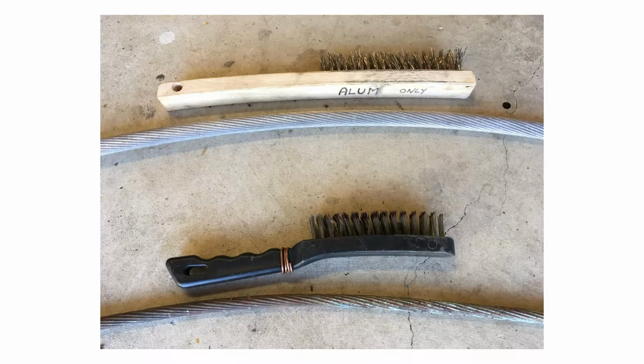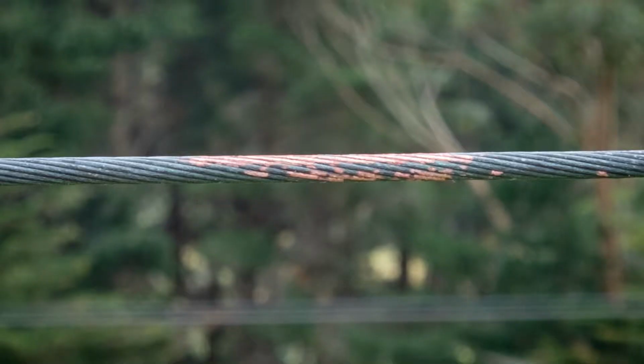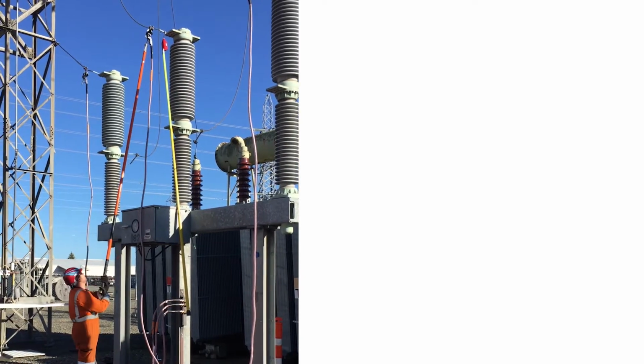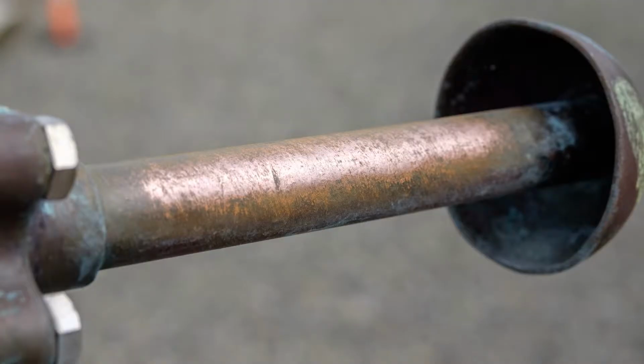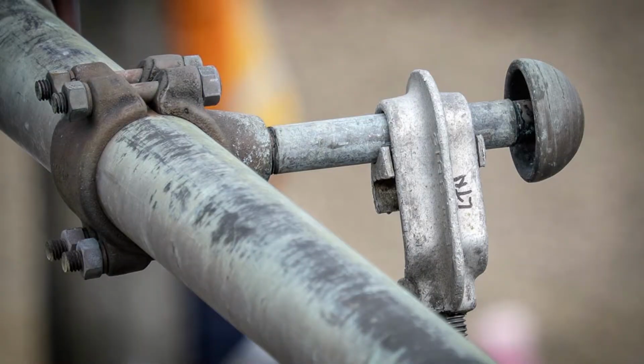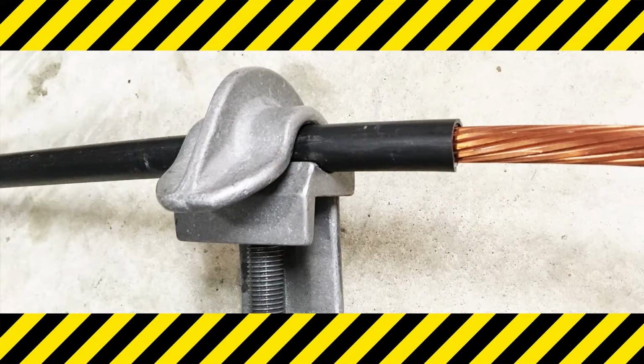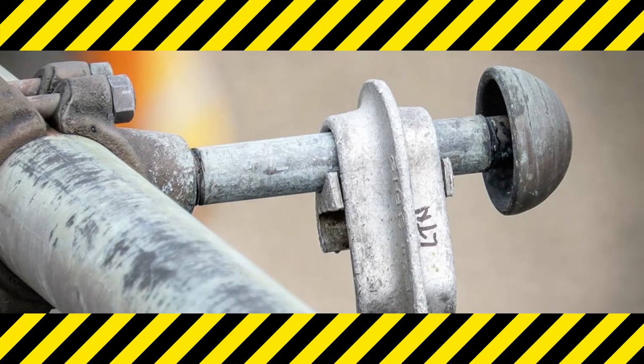Make sure that you have a brush for cleaning copper conductor and a separate brush for cleaning aluminium conductor, so that you don't cross-contaminate the brushes. In the case of badly contaminated copper conductor, you might need to use something even harder than a brush to clean off the oxide. In substations, the same cleaning rules apply, and cleaning earthing horns is just as important. Copper and aluminium earthing horns can become oxidized and should always be cleaned before earths are applied. You wouldn't put a earth clamp on this, so why are you putting one here and here?